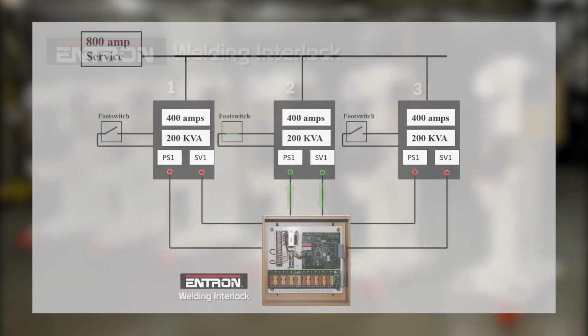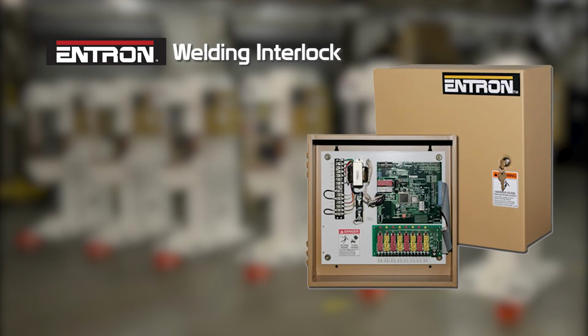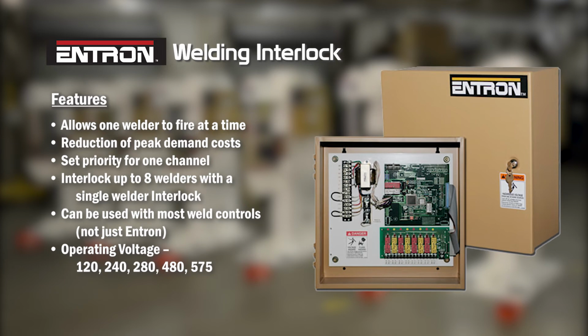Let's review some of the features of the interlock. Welder interlocks allow you to minimize the demand on a power service by allowing only one machine to fire at a time. This allows you to add extra welders to a limited power service or reduce peak demand cost. You can interlock up to 8 welders with a single welder interlock.